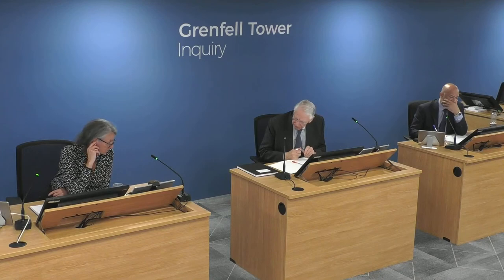I'm sorry, before we go on, just help me understand the mechanics of this. If dampers are open on a higher floor and the fans are running, isn't the airflow going to be from the lobby into the shaft? There would be some airflow from the lobby into the shaft, but exactly how much can be achieved will depend on the flow resistance pathway.